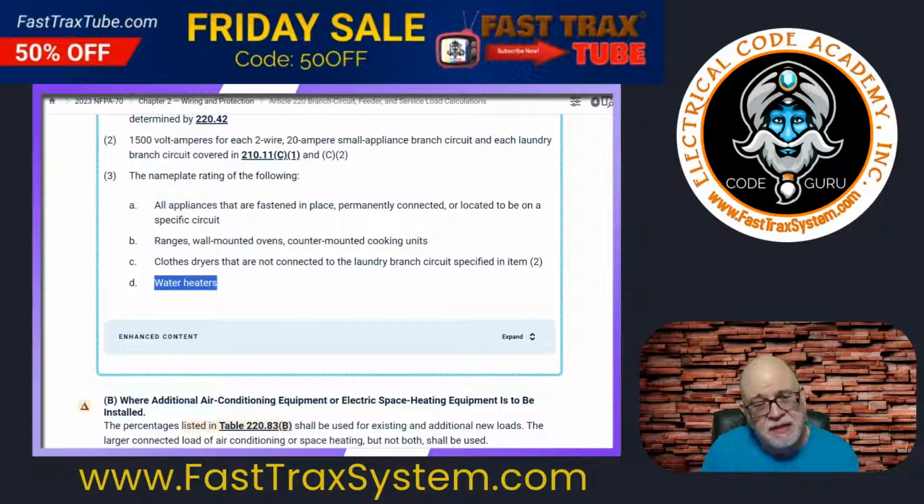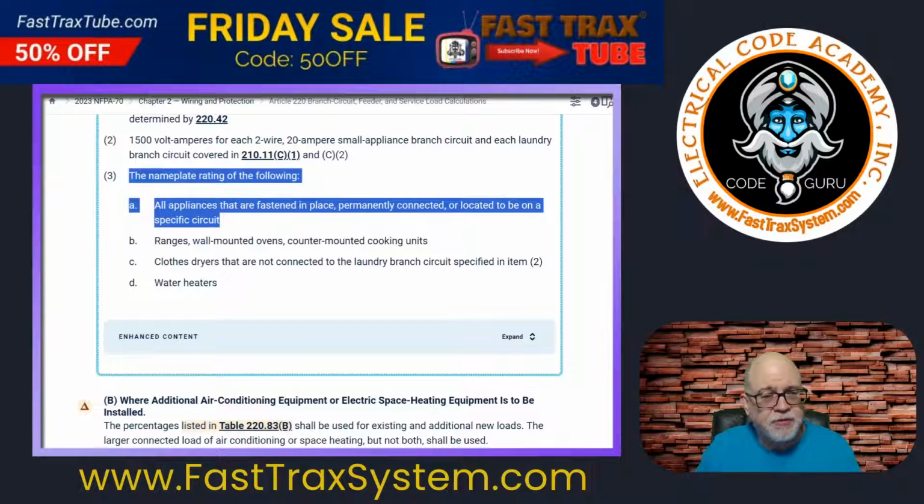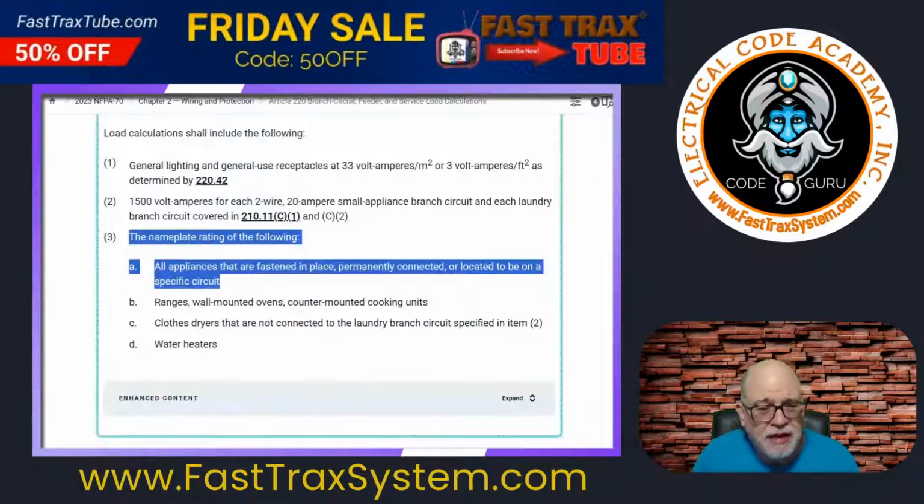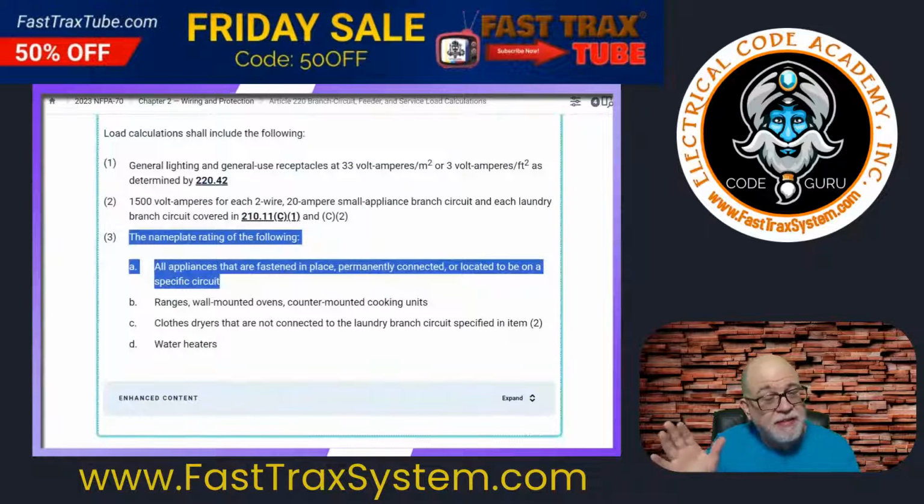So what we're doing is we're simply taking the actual nameplates of all of these. We're adding all of this up. And remember, this is where people get confused. If there is existing heating and cooling, you go and you add that information as well into here. That all falls under 3, and more specifically 3A of the 2023 edition of the National Electrical Code. Straightforward, right? Makes sense. And that's what's going to determine whether or not you have the capacity. So basically, this is just like an optional method, that type of thing.